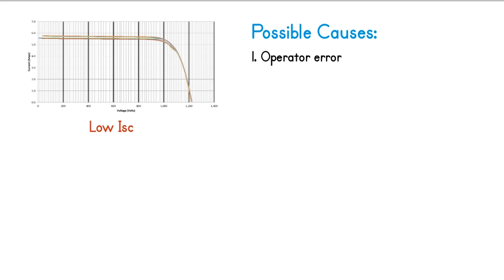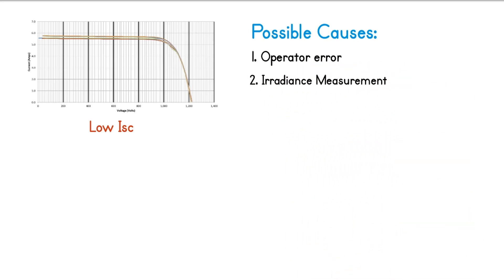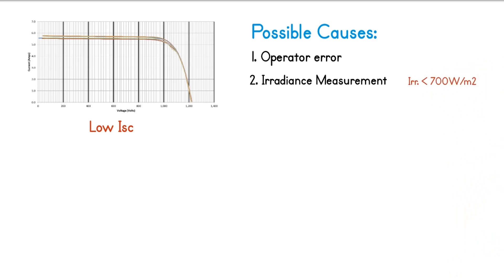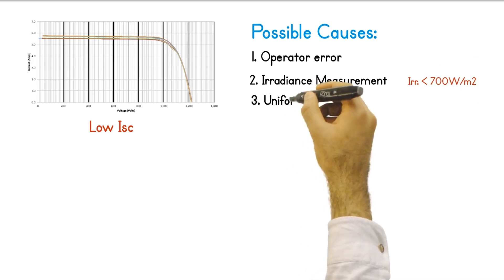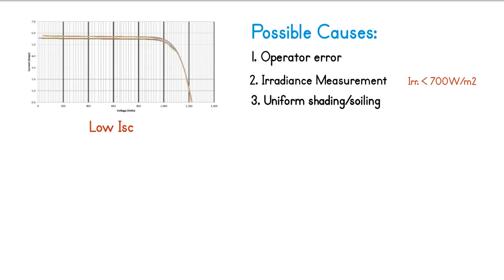Second possible cause is irradiance measurement issues. This is a common cause of error during IV curve tracing when the irradiance meter is not installed properly on the plane of array, or when the test is performed when there is low irradiance below the recommended level. Third cause of low ISC is uniform shading or soiling, or even module performance issues.